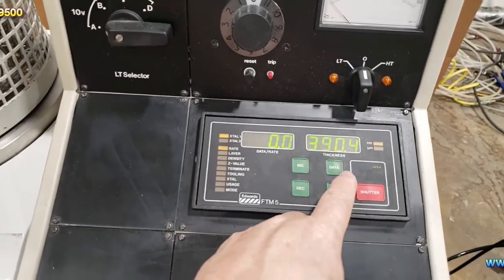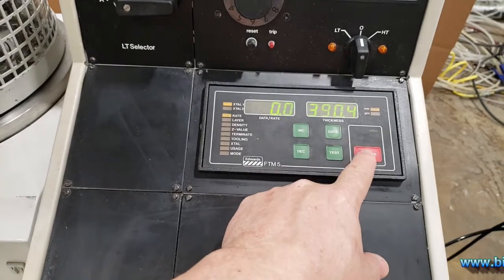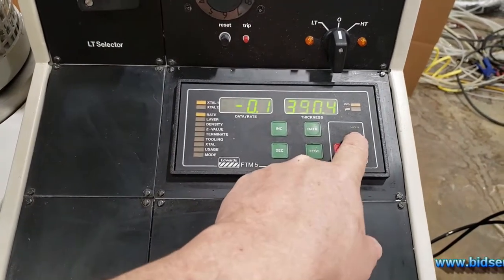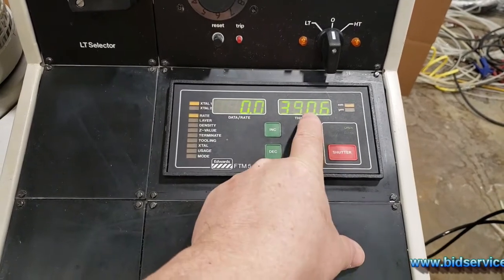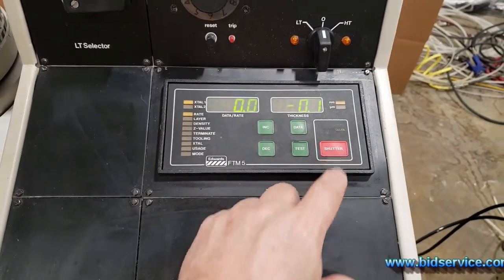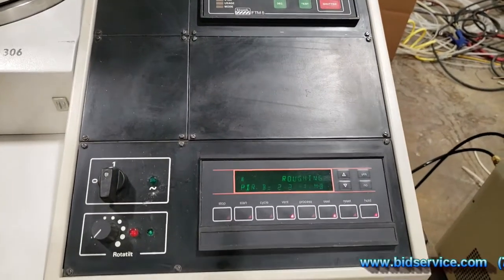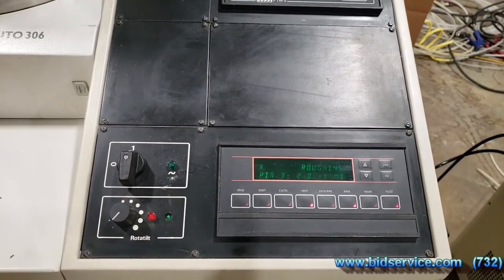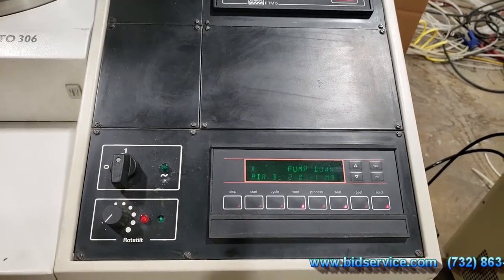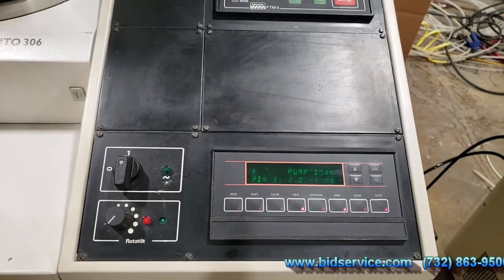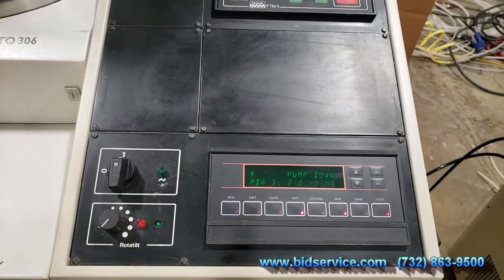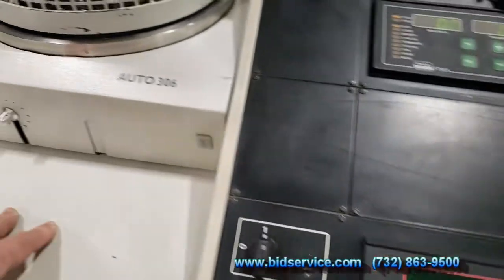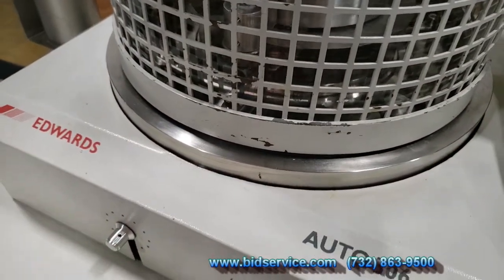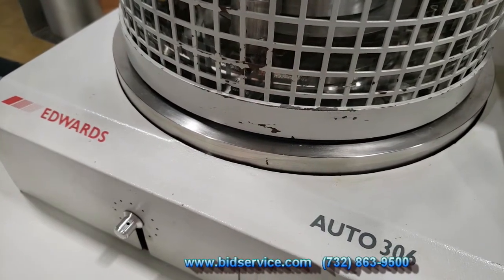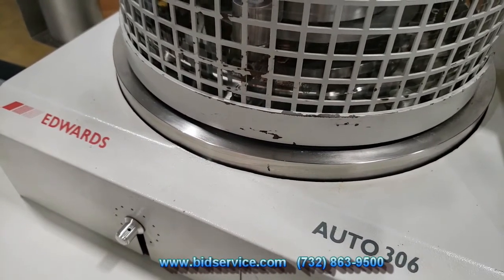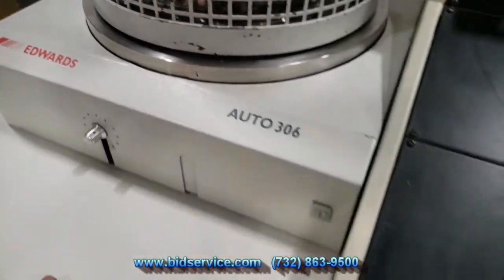Now, as you can see up here on your deposition controller, it says 39, that's your total thickness. If you just want to reset that, you just want to go to here where it says close and then open again, and it will zero itself out. That clicking noise is because it's right now trying to go into high vac. And if you look down below, you'll see the high vac valve getting ready to open up. And you can see it rising right there. And now you're under high vac.